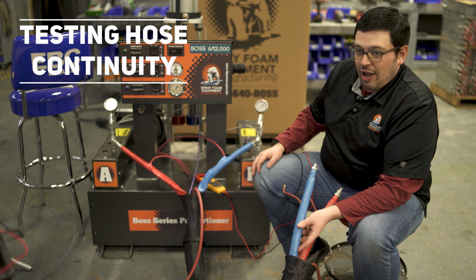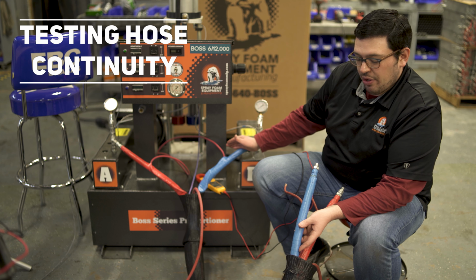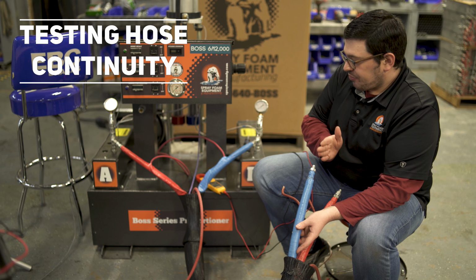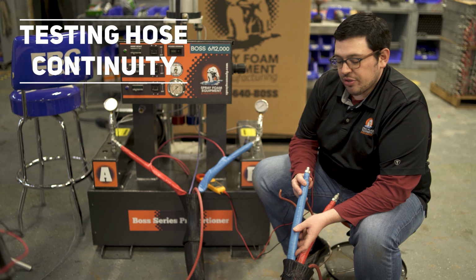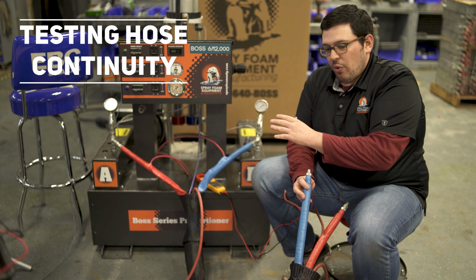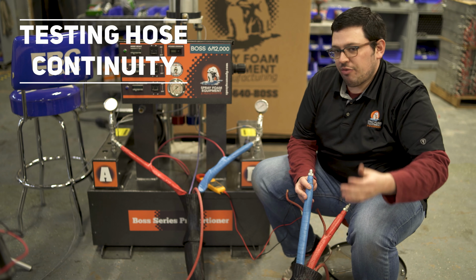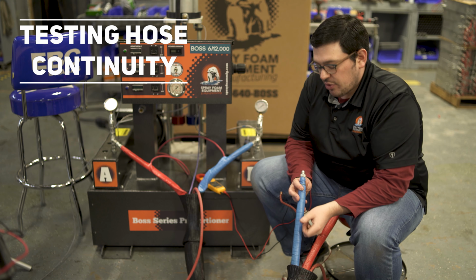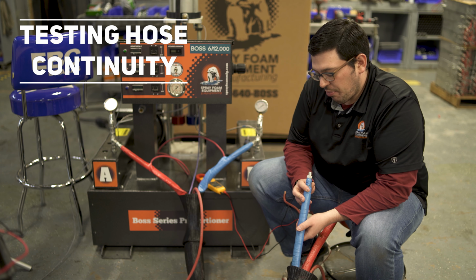If you don't have continuity still within that first half of the hose, then you know, okay, my break is somewhere in the first half of the hose. And then you just work your way back from each midpoint, either from that point down to the end of the hose or from that point back to the machine, to try and determine exactly where the break is.